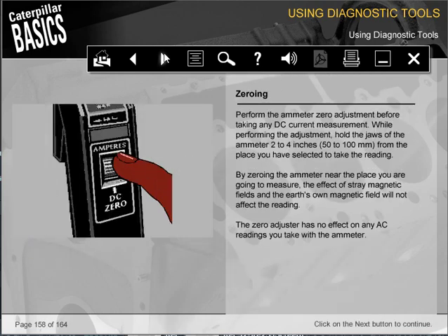Perform the ammeter zero adjustment before taking any DC current measurements. While performing the adjustment, hold the jaws of the ammeter 2 to 4 inches, 50 to 100 millimeters, from the place you have selected to take the reading. By zeroing the ammeter near the place you are going to measure, the effect of stray magnetic fields and the Earth's own magnetic field will not affect the reading. The zero adjuster has no effect on any AC readings you take with the ammeter.